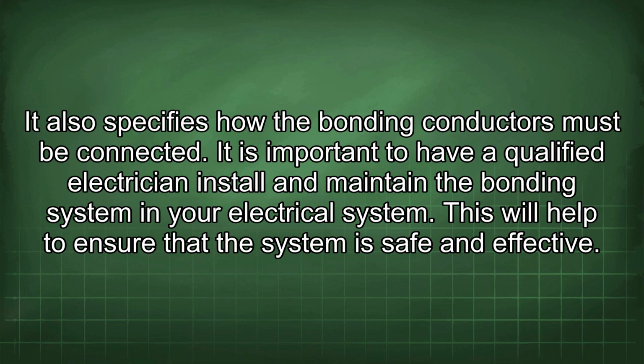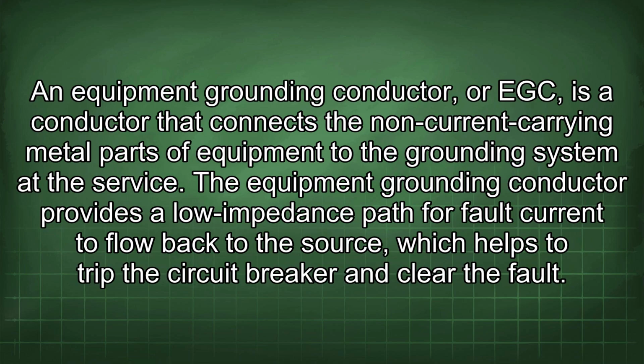It is important to have a qualified electrician install and maintain the bonding system in your electrical system. This will help to ensure that the system is safe and effective. An equipment grounding conductor, or EGC, is a conductor that connects the non-current carrying metal parts of equipment to the grounding system at the service. The equipment grounding conductor provides a low impedance path for fault current to flow back to the source, which helps to trip the circuit breaker and clear the fault.